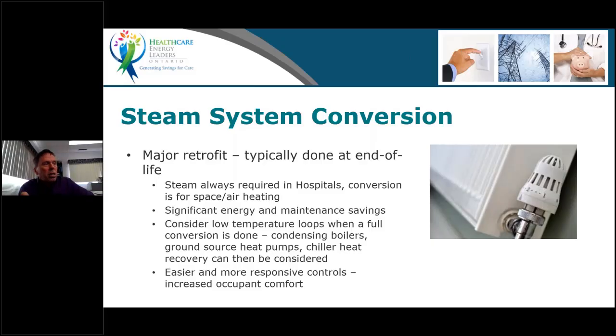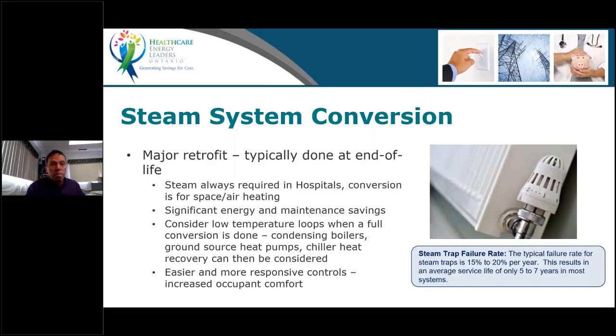There are exceptions where you have a really good steam system that can maintain proper conditions, but they are more difficult and they have steam traps. And when you talk steam traps, we're going to see there are a lot of potential losses. But that's not a low cost measure. That's something you must consider as a significant retrofit. And Paul might see it differently, and is welcome to talk about that later on. But usually steam conversion is something to consider at the end of the useful life of the system.